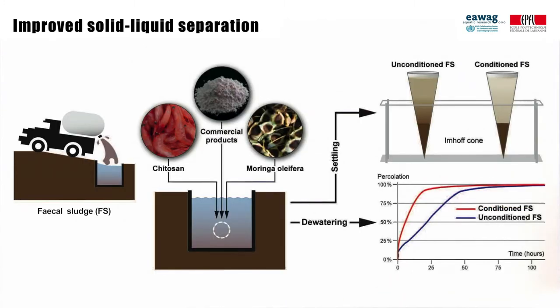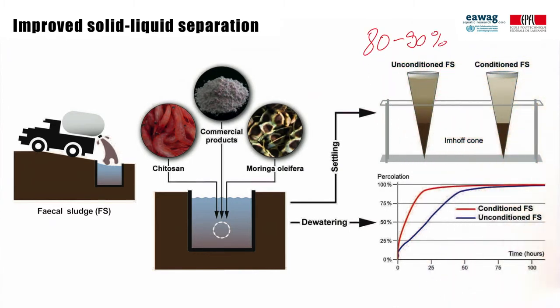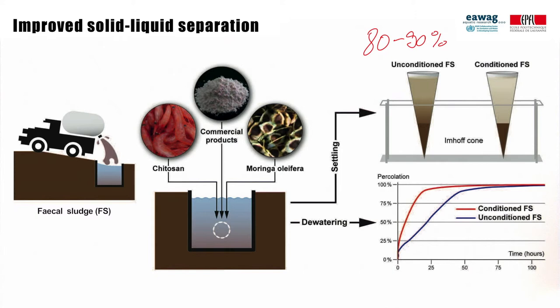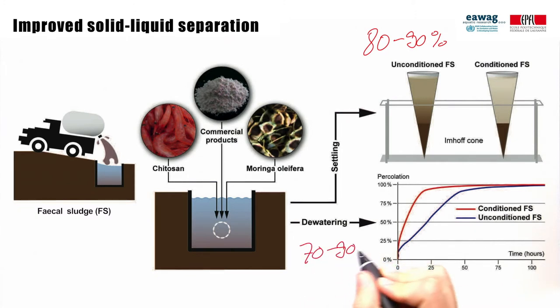In this study, conditioning of septic tank fecal sludge could reduce the suspended solids in the effluent of settling thickening technologies by 80 to 90 percent. The dewatering rate on drying beds, for example, could be improved by 70 to 90 percent. This could reduce the dewatering time of sludge on drying beds by 60 to 95 percent.